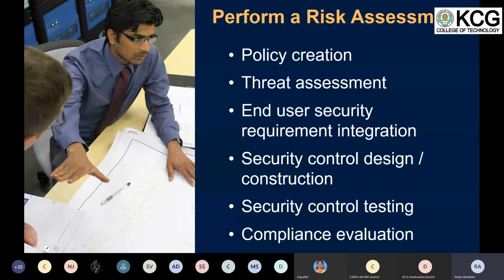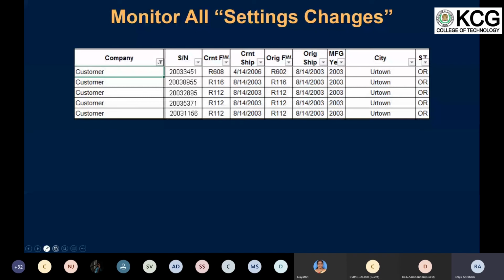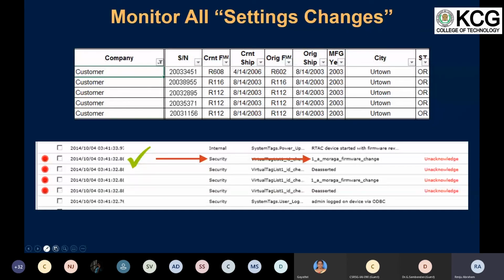Any setting change, any setting which is being sent to a relay or a controller or any other device, should be monitored. The relays usually come with an inbuilt node which detects any change in the settings, or if anyone has logged in or out, changed any setting, sent the setting, or read the setting. That logical node or address can be assigned to the relays to monitor it regularly over the syslog protocol, which is the system log protocol. So all the data can be connected to a centralized syslog server, and then the operator can monitor any system change in the network.